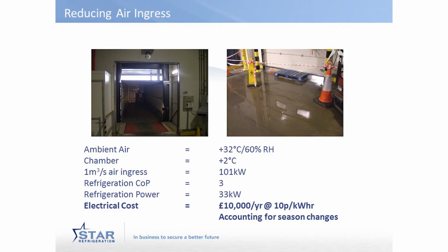In this one, a truck is backed up to the cold store door, and you can see there's a gaping hole above because they've backed a small truck up to a big door and they've not made use of the baffles or curtains to block it out. Now that looks okay. You think, well, there's probably not much of a draft coming in there, but in addition to the air coming in from outside, the air coming in from outside is carrying moisture with it.